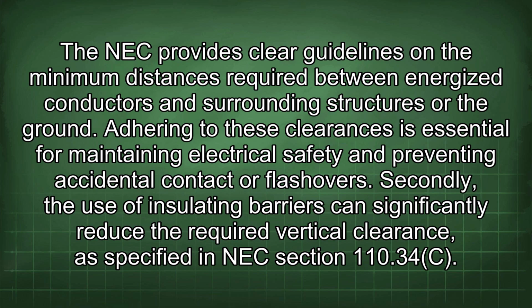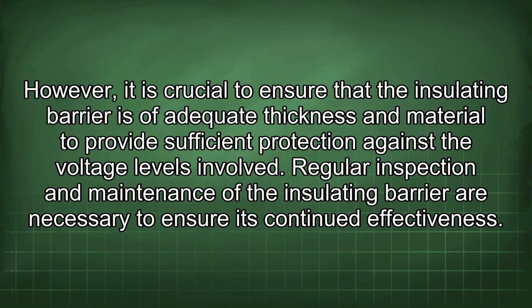Secondly, the use of insulating barriers can significantly reduce the required vertical clearance, as specified in NEC section 110.34C. However, it is crucial to ensure that the insulating barrier is of adequate thickness and material to provide sufficient protection against the voltage levels involved. Regular inspection and maintenance of the insulating barrier are necessary to ensure its continued effectiveness.